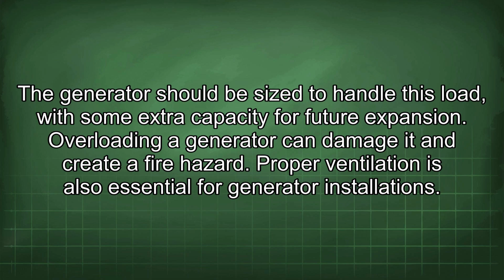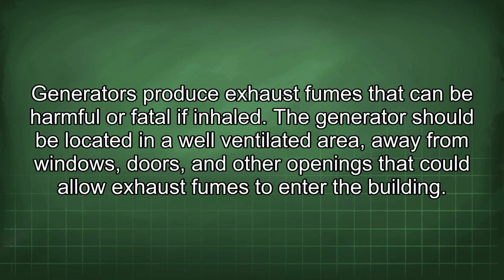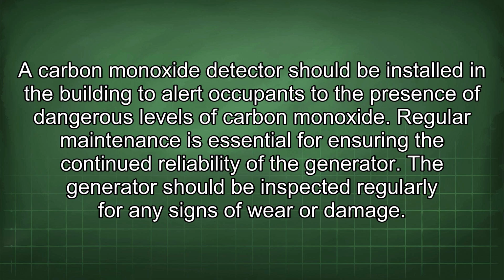Proper ventilation is also essential for generator installations. Generators produce exhaust fumes that can be harmful or fatal if inhaled. The generator should be located in a well-ventilated area, away from windows, doors, and other openings that could allow exhaust fumes to enter the building.